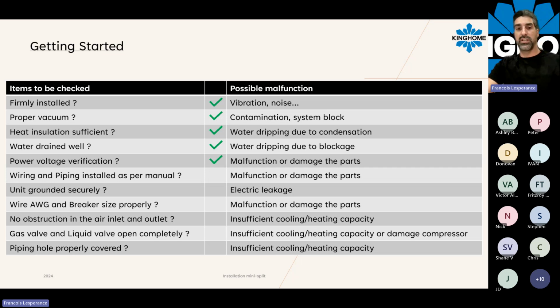You have checked your power voltage when you have done all your tests. The wire gauge and the piping are installed as per manual. So that's really important, to respect the manufacturer settings. The unit is properly grounded. You have checked your breaker size, so make sure that will not create some dysfunction or damage in a couple of years from now. You have no obstruction at your air inlet or air outlet. Your gas valve and liquid valve are open completely. And also the piping hole is properly covered.